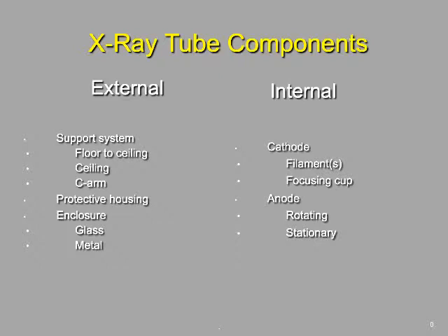The enclosure may be made out of glass, Pyrex, aluminum, or some low-Z metal, and its primary purpose is to provide a vacuum. Internal to that enclosure is the cathode — the negatively charged portion with filaments and focusing cup — and opposite that, a rotating anode. Stationary anodes are largely used in dentistry, where the machines are much quieter because no part is rotating.